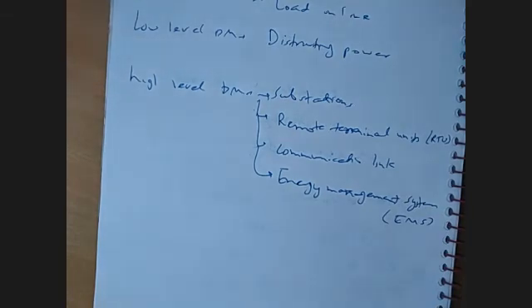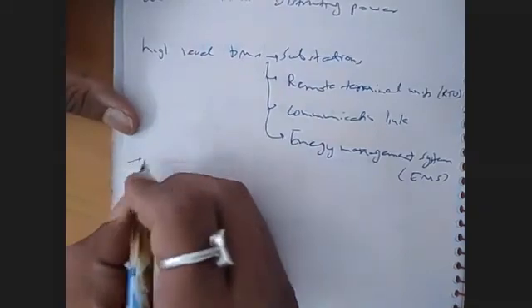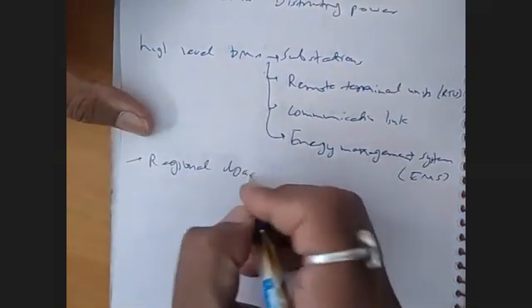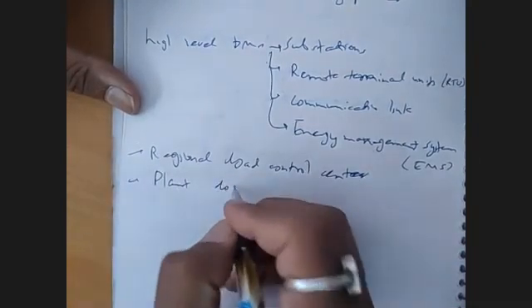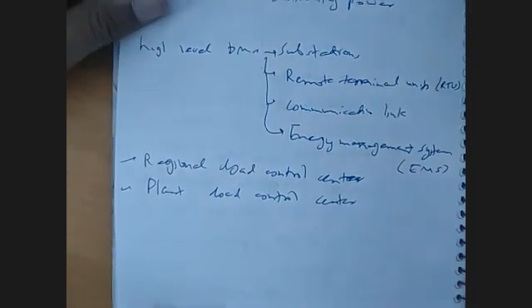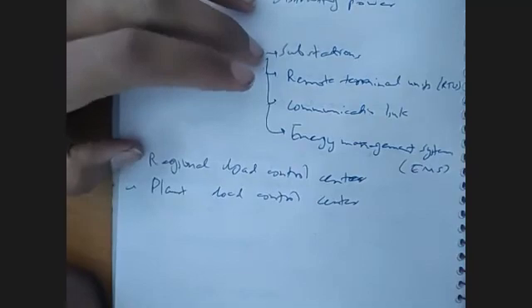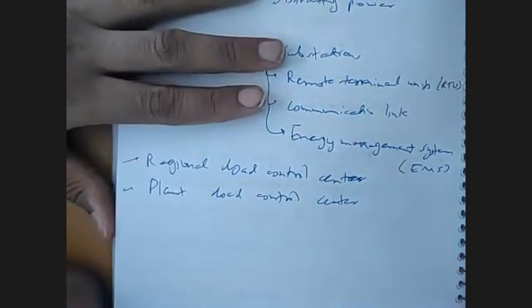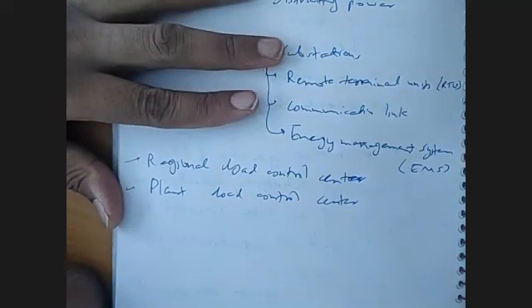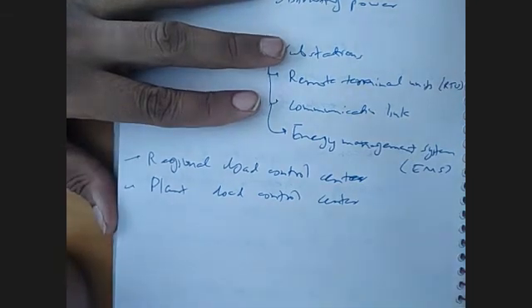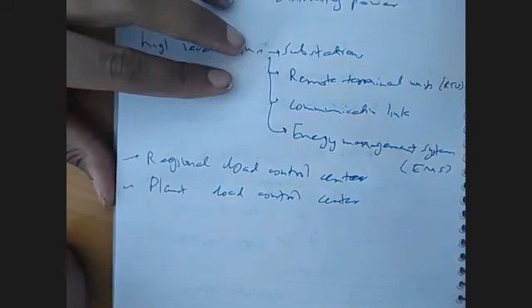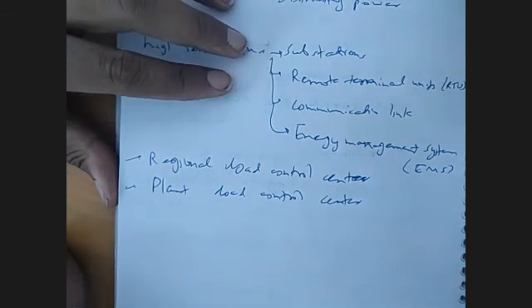So for energy control centers, we can have various levels or various types of energy control system. First, we have regional load control center. Then we can have plant load control centers. So when we are talking about regional load control centers, it will decide the generation allocation to various generating stations within the region on the basis of equal incremental operating cost, considering line losses as equal, and frequency control in the region. So regional load control centers will be deciding how much generation.